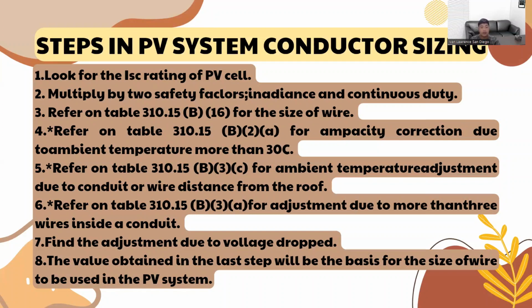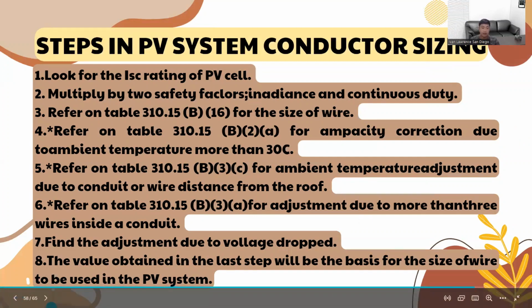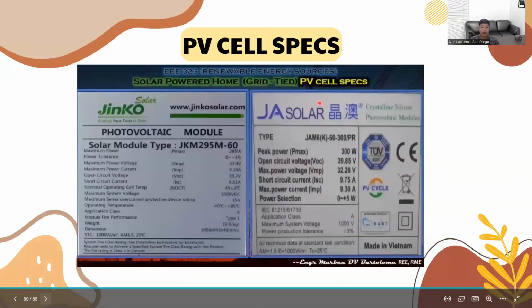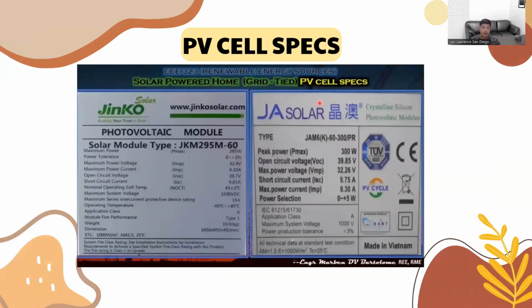5 is refer on table 310.15b3c for ambient temperature adjustment due to conduit or wire distance from the roof. And 6th step is refer on table 310.15b3a for adjustment due to more than 3 wires inside a conduit. And 7 is find the adjustment due to voltage drop. And number 8, the last step, is the value obtained in the last step will be the basis for the size of wire to be used in the PV system. These are the types of PV cell specs.